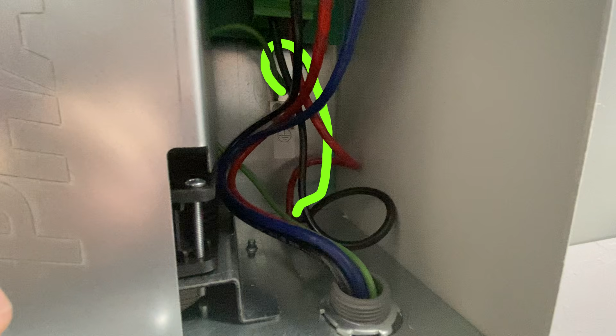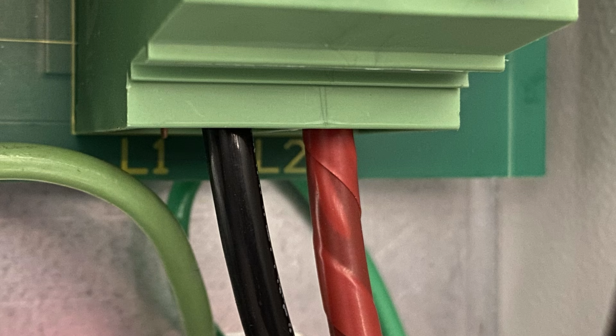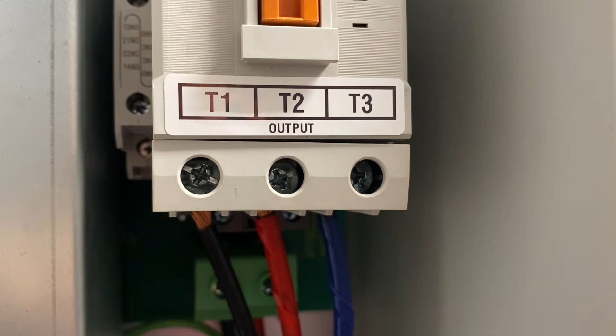Now, just like the switch, the green ground wire connects to the metal box and then passes through. The red and black wires connect to a green terminal box under the white output box. The black wire goes to L1 and the red goes to L2. So we now have a blue wire added to the red, black, and green group of wires going to the transformer. The black is coming from T1, the red is coming from T2, and the blue is coming from T3. 3 wires come into the phase converter, 4 wires go out.